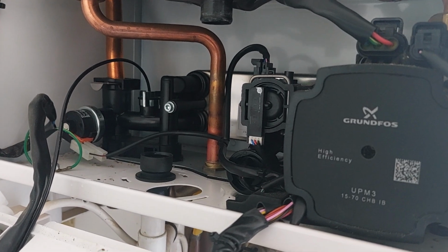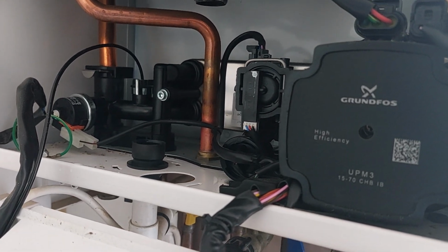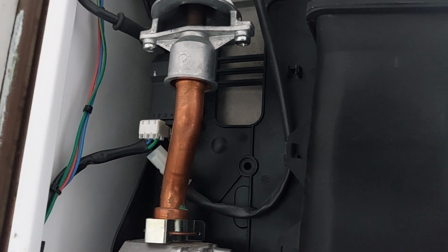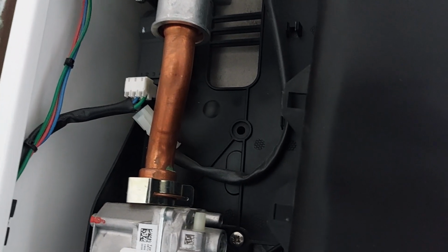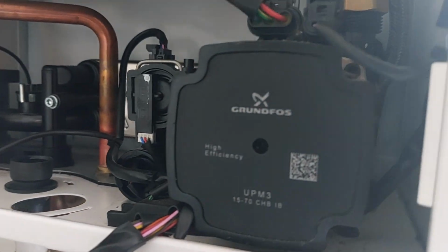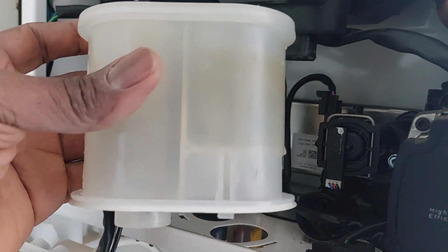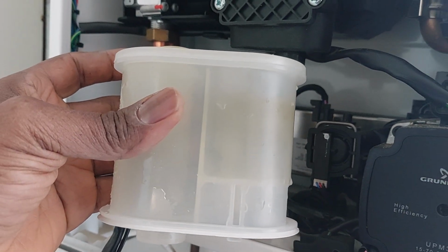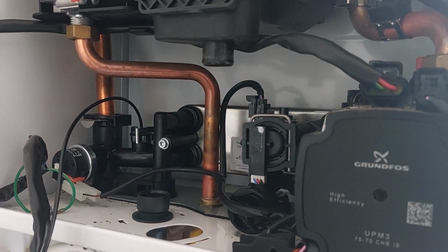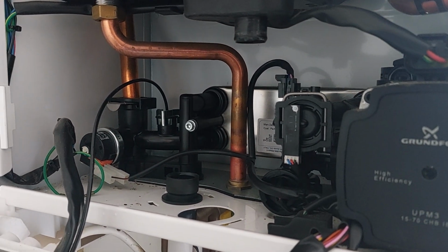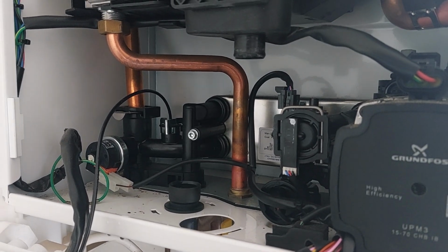And yeah, that should probably be it. So that's what we did. What we did earlier was replace the igniter first, just by referring to YouTube, and that didn't solve the problem. So it was the condenser trap. So this video is going to be entitled L2 error message on an Ideal boiler. This is probably the first thing that you should try to solve the problem.